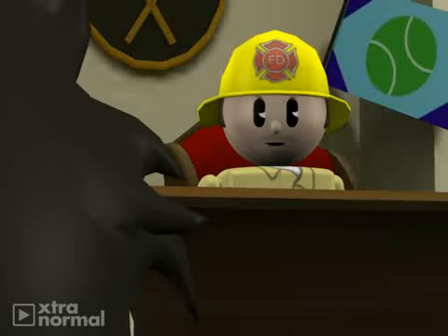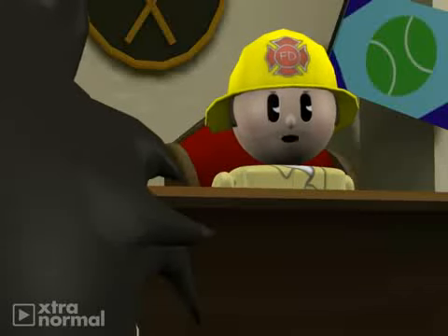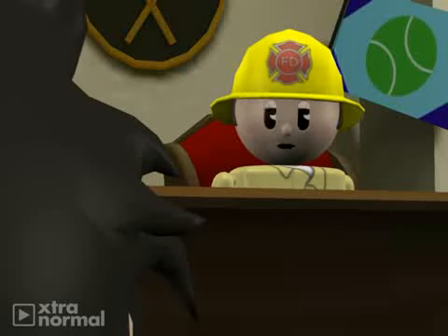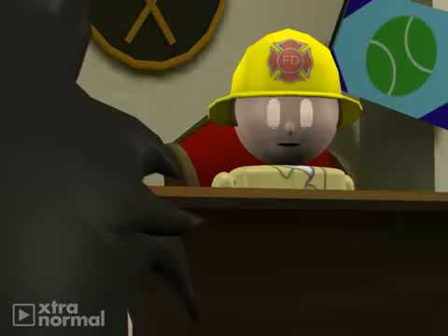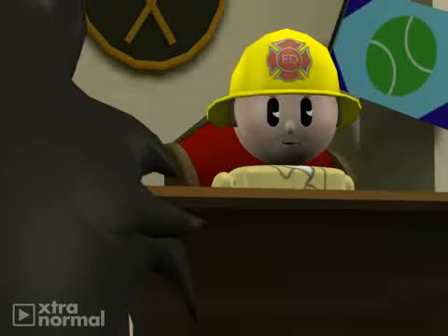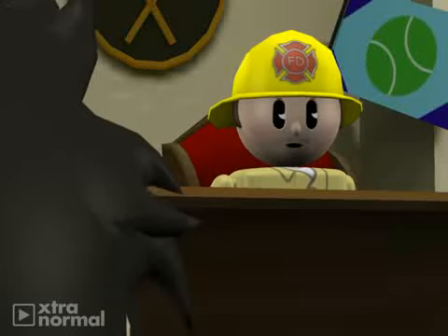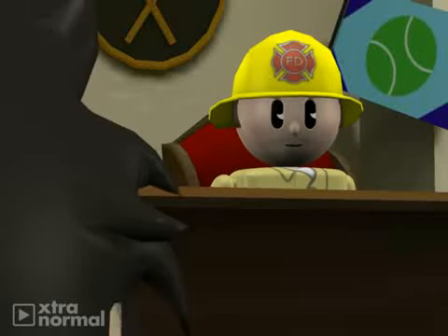Water mist systems fight fires and protect the surroundings primarily by evaporation of water in and around the fire plume. The evaporation of water takes large quantities of energy which cools the flames and reduces the net heat output of the fires, and the steam created helps smother the fires. Therefore, for fires in open space, water mist systems perform best when delivering water droplets in sizes which are large enough to penetrate into the fire plume and small enough to evaporate inside the fire plume.